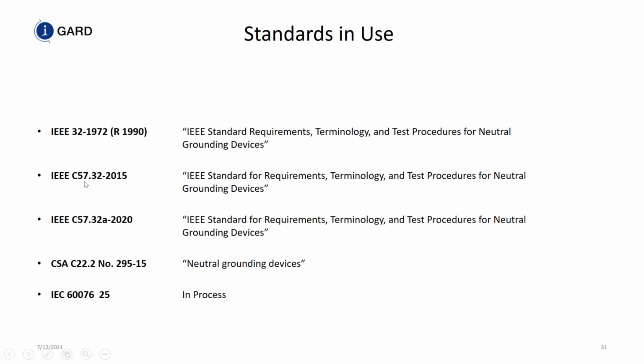It was rewritten in 2015 and became IEEE C57.32, same title, but it replaces IEEE 32. An amendment was made to this standard for some trivial items. CSA has C22.2 number 295, neutral grounding devices, and IEC standard 60076 part 25 is in process, and it will basically be a standard for requirements, terminology and test procedures for neutral grounding devices. The only one that's just a product standard is CSA C22.2 number 295, because CSA uses it to evaluate neutral grounding devices, whereas all the other standards are used as a guide for terminology.